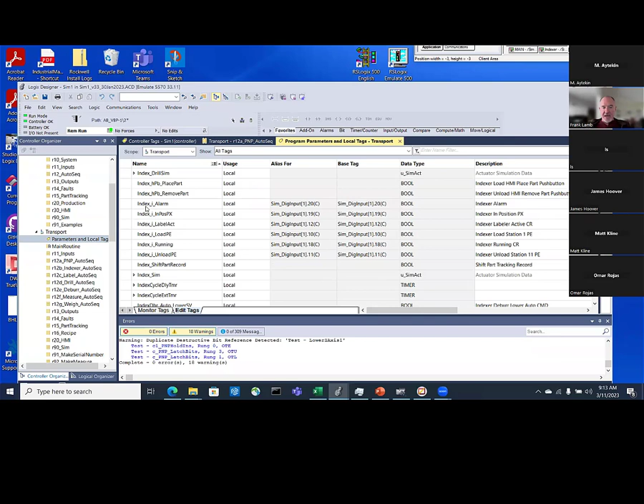You can do the same for analog. So I've connected these to fake IO, and all you have to do if you had a real program here and you were simulating it is go back in after you tested everything and it works well and re-alias all of the fake IO back to the real IO. And then you've tested your program, it's run, you've actually seen it on the screen, operate mechanisms and things like that. You've watched part tracking and you know everything works. Then you finally get to power up your machine and you download the program and it's aliased to real IO and it just runs.